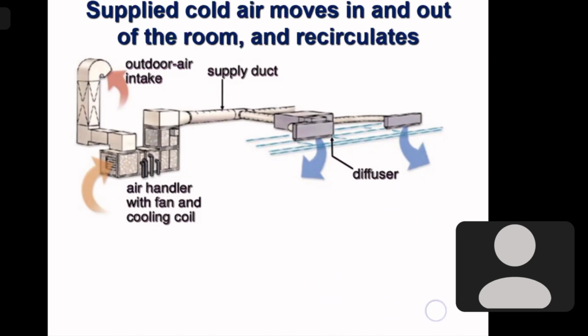We are allowing it to leak out from the room through wherever there are openings, like from the bottom of the door, from around the window. If somebody opens the door and goes out, air will only come out from the room. The room will remain in a little over pressure, slightly above the ambient pressure. So whenever there is an opportunity, air will only leak out from the room. No outside air can enter the room when you open the door, or if there is a leakage source or an opening. Air will only come out.